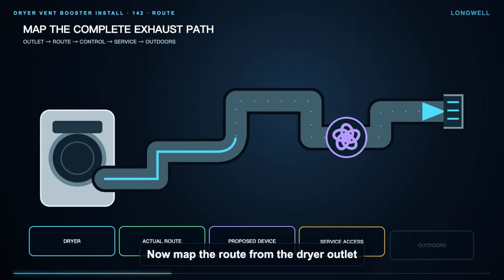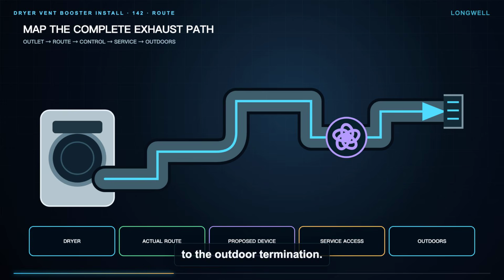Now map the route from the dryer outlet to the outdoor termination. Record the actual duct path, changes in direction, accessible joints, existing restrictions, the proposed ventilator location, the control relationship, and the service approach. Do not copy a universal length, elbow deduction, airflow target, or placement distance from another model. Those limits come from the exact dryer and ventilator instructions plus the applicable local review. The map exists to expose unknowns before hardware is fitted.